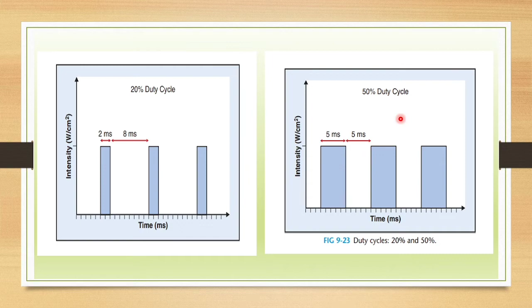Coming to the duration, the treatment duration is selected according to the treatment goal, the size of the area to be treated, and the effective radiating surface area of the ultrasound head. For most thermal or non-thermal applications, ultrasound can be applied for 5 to 10 minutes for each treatment area that is twice the effective radiating area of the transducer. For example, when an area measuring 20 centimeters square is treated with an ultrasound head that has an effective radiating surface area of 10 centimeters square, the treatment duration should be 5 to 10 minutes. So usually we apply for nearly 8 minutes. That is the normal protocol.